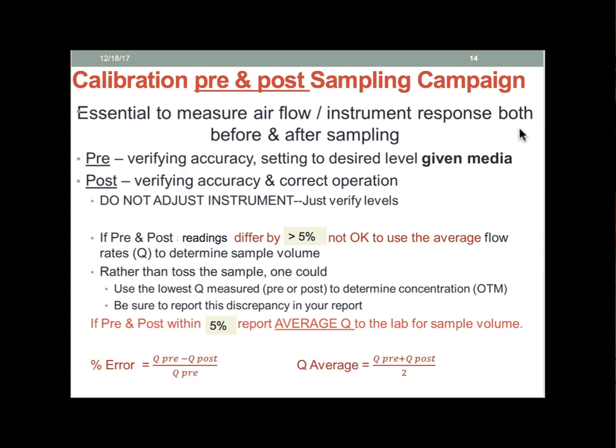So we calibrate before we sample — pre-calibration — to set the appropriate flow rate, which is also a check to see if our pump is performing appropriately. After we're done sampling, we post-calibrate our pump as soon after the sampling campaign ends as possible. We don't make any adjustments to our pump — we just check the flow rate to see if it's within a certain range. If it differs by too much, we might not be able to use our data. Also, we need to calculate a sample volume to send to the lab, which will be based on our flow rate and the time for which we sampled.